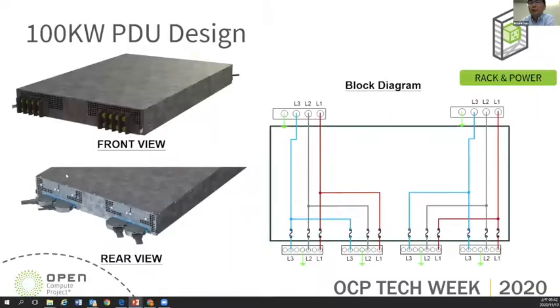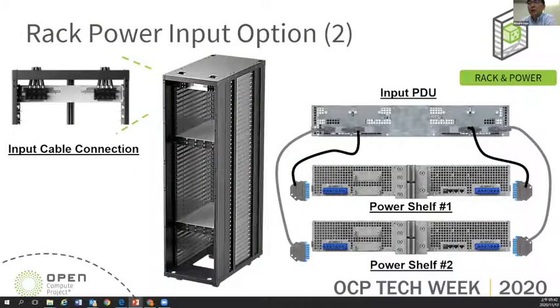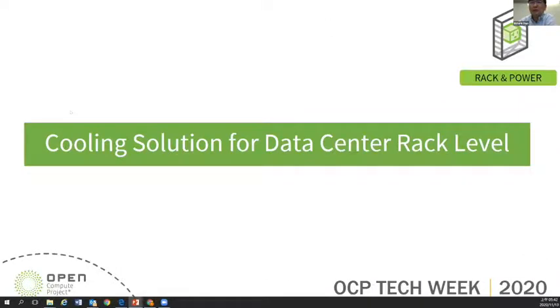And the other approach is we can design a 2U PDU. This PDU has 2 inputs and 4 outputs. And these 4 outputs are connected with the power shelf. And you can see from the rack rear side, we have 4 cables connected with this power shelf. And from the input side, we just use a power data center input cable directly connected with the input terminal block. And this input block can be a single 1 or 2. Then we can do some custom design modification for that. It's not so complicated. And following, I will arrange to introduce some of the cooling solution for this high power rack.